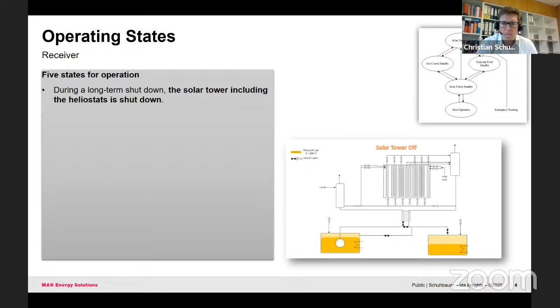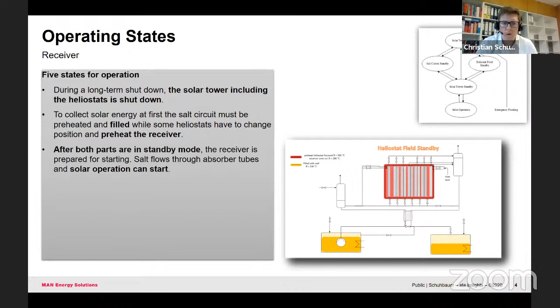And in the next step, we have to get into the salt circuit standby. That means the pipelines are preheated via heat tracing, and we can pump the salt via the inlet vessel back again to the cold storage tank. So this cycle holds everything on temperature, and in parallel, the receiver itself is preheated by some heliostats, which heat up the receiver system up to 350 degrees C. And if these boundary conditions are fulfilled and everything is in standby mode, the receiver is prepared for starting.